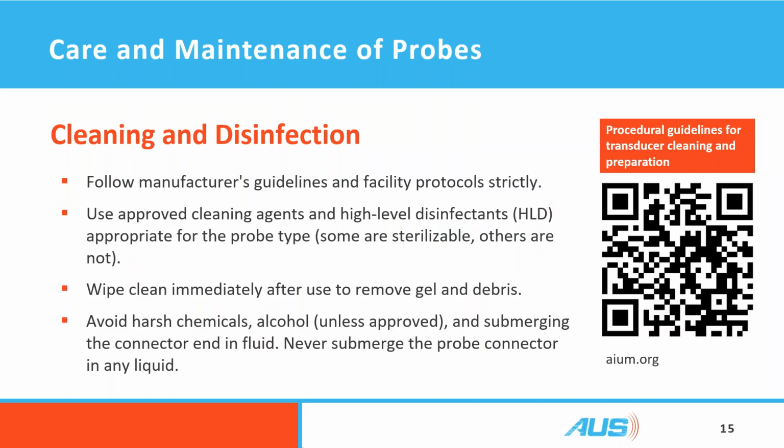You should avoid harsh chemicals when they're not needed. Alcohol, unless it's approved for that type of probe. Submerging the connector. People say, well, that never happens. Well, that's not true. I was at a hospital and one of the surgical nurses was told to go ahead and sanitize the probe, and she put the whole probe in the solution.